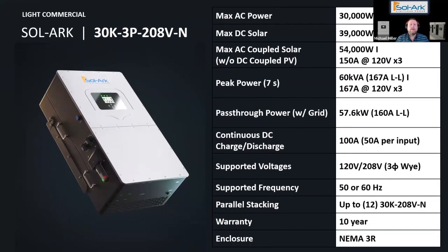So taking a closer look at our 30K, which is available, 30,000 watts is what the 30K lines up with. 130% oversizing on the solar array, so we can take up to 39,000 on the DC side. And then we could AC couple as well on these inverters, 54 kilowatts, and that is the AC rated power. So it could be more actual DC power. So you could have a mix of those as well.